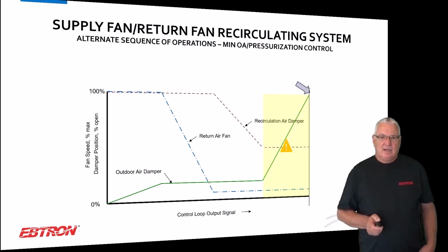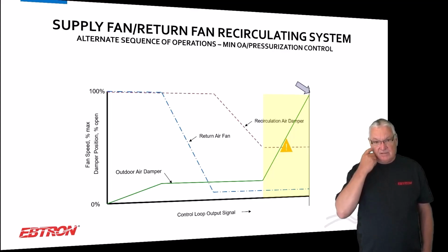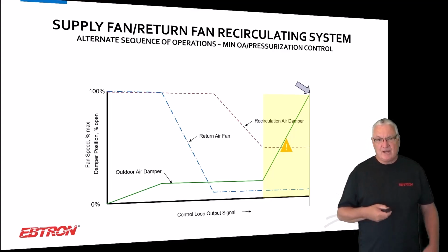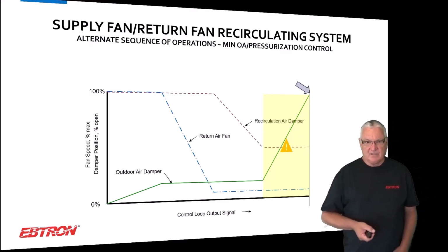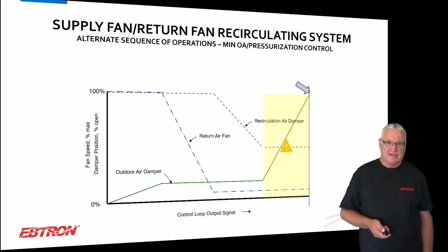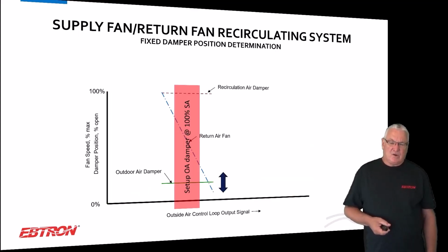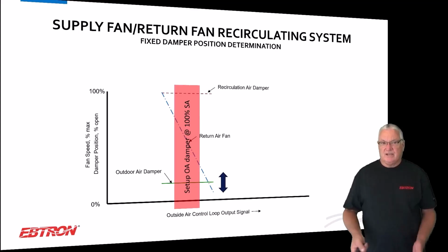All right. And again, somewhere in this yellow range, you do have to be careful how far you let the recirc air damper close before you open the outside air damper. Setup: you say, well, you have this fixed outdoor air damper position, how did you find that?